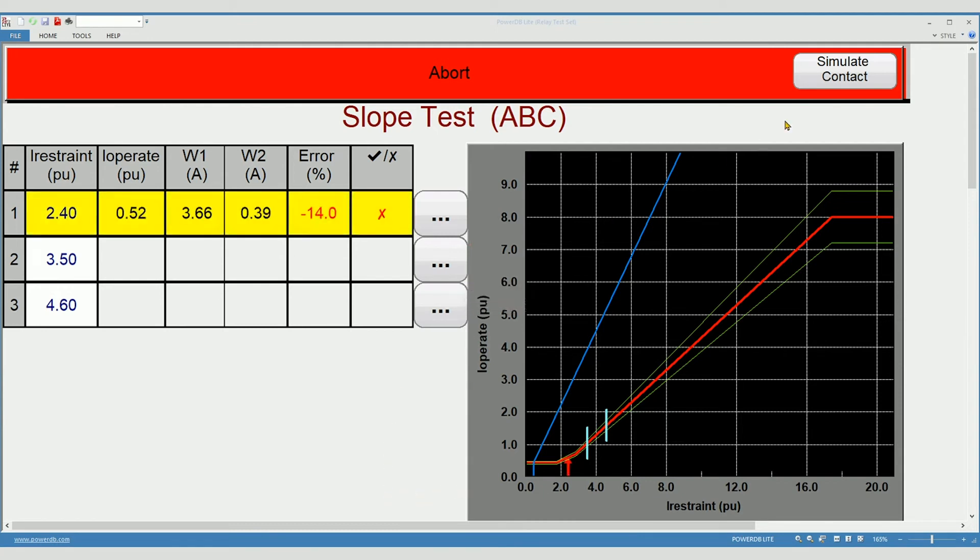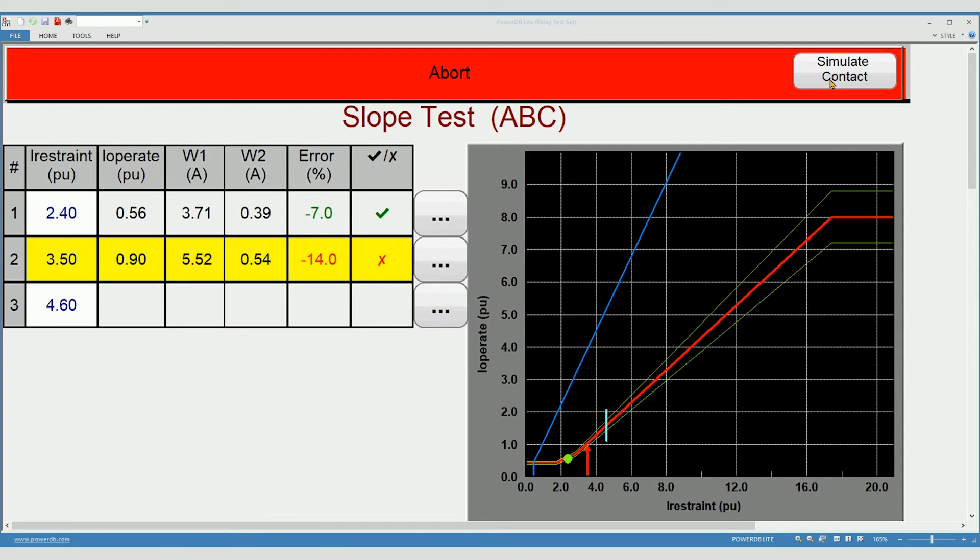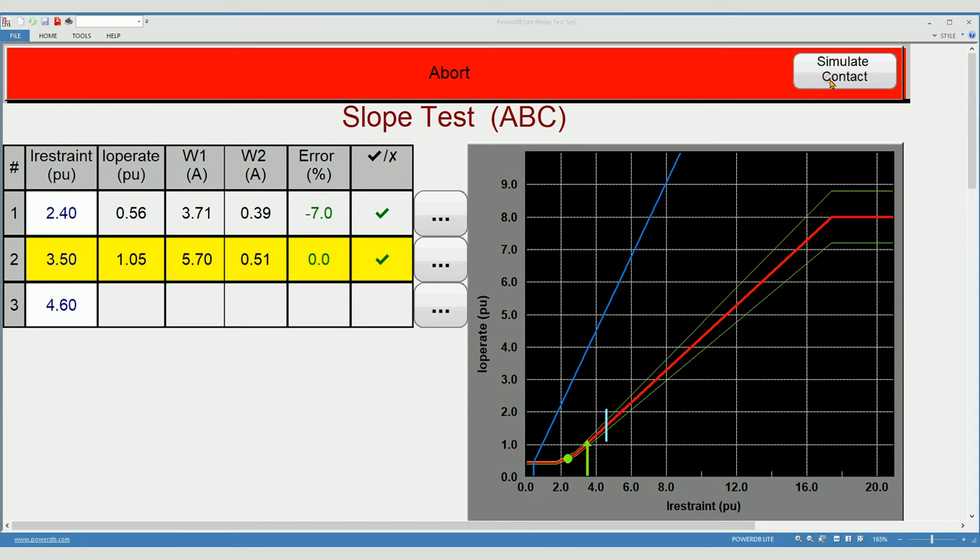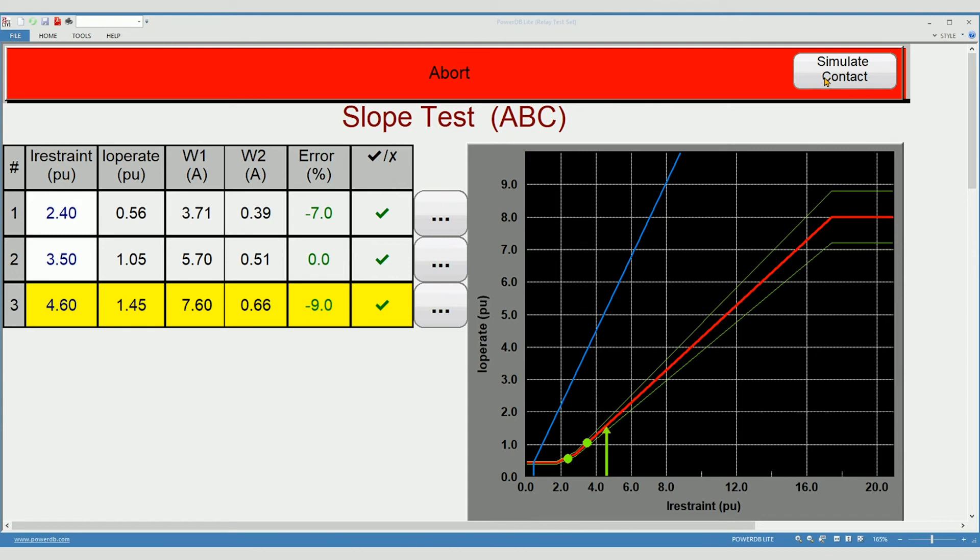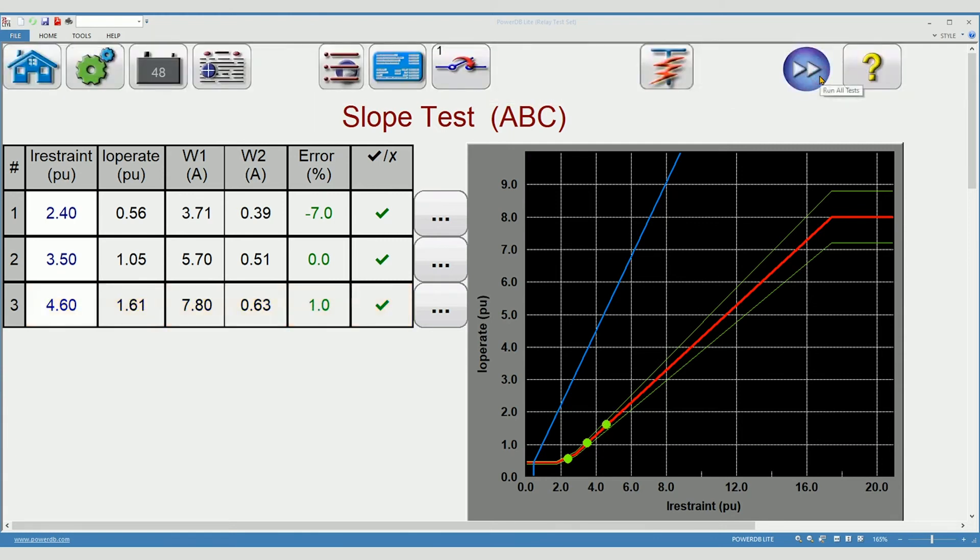Current is being applied to the relay. When the arrow turns green, I know it's a passing test. That's when your contact should close, I will simulate. It's moving into slope two now. And the final test will begin. And the characteristic slope test is complete.